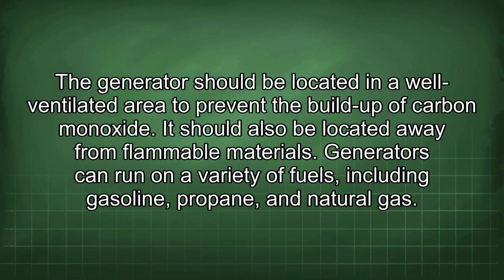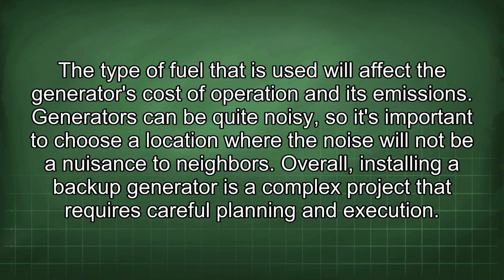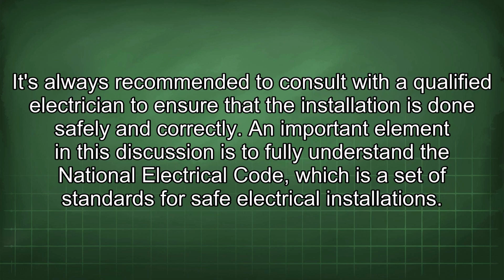Generators can run on a variety of fuels, including gasoline, propane, and natural gas. The type of fuel that is used will affect the generator's cost of operation and its emissions. Generators can be quite noisy, so it's important to choose a location where the noise will not be a nuisance to neighbors. Overall, installing a backup generator is a complex project that requires careful planning and execution. It's always recommended to consult with a qualified electrician to ensure that the installation is done safely and correctly.